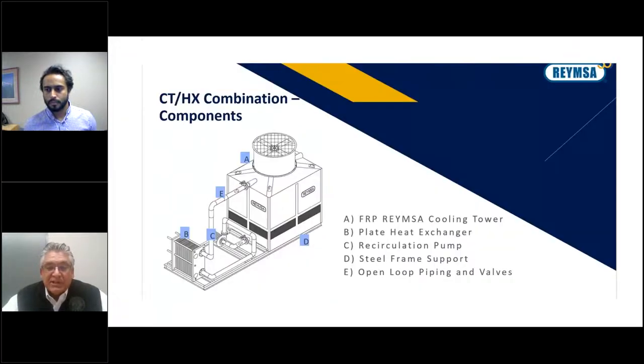But to continue that conversation, I think Ali mentioned we do have REYMSA. It's a fiberglass cooling tower. We have Polaris heat exchangers, but also REYMSA will actually fabricate pipe and put all the valving on the cooling tower for a free cooling application where you're going to use chill water through a plate frame heat exchanger. So that's also another option for free cooling.